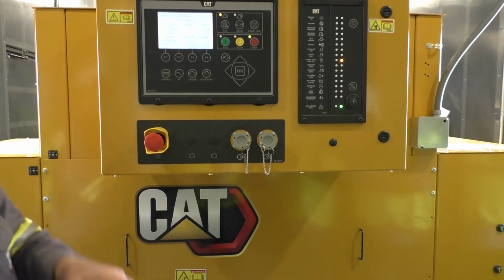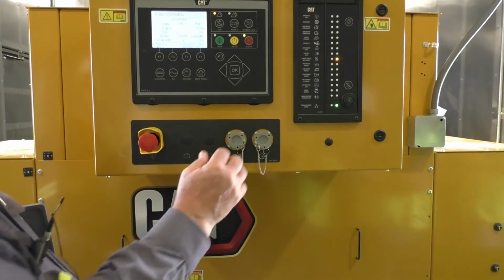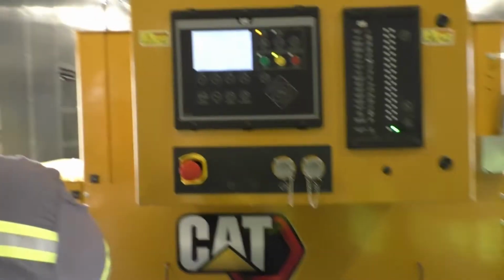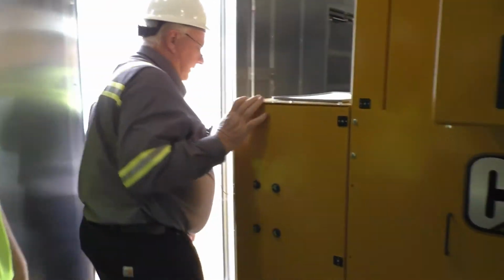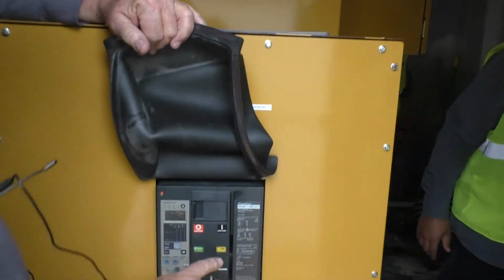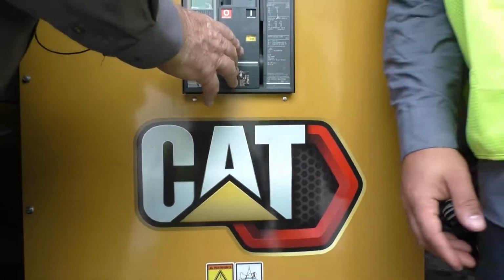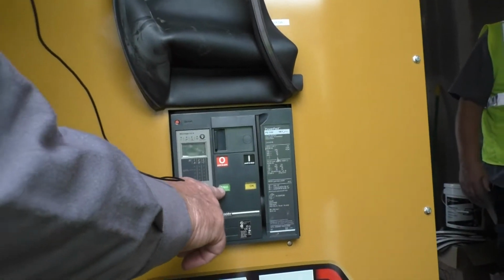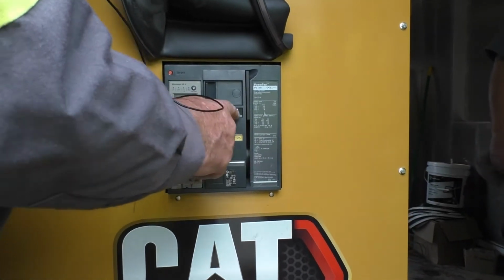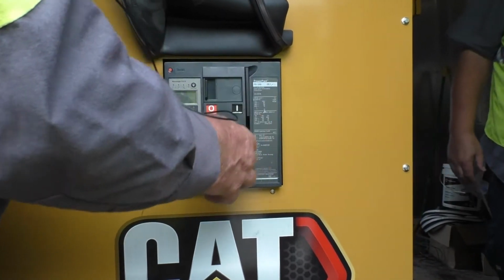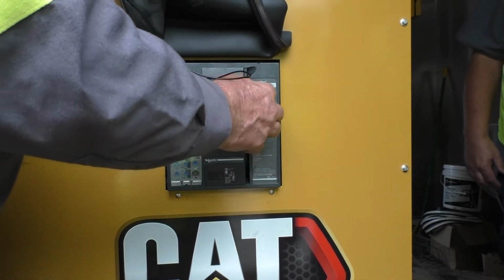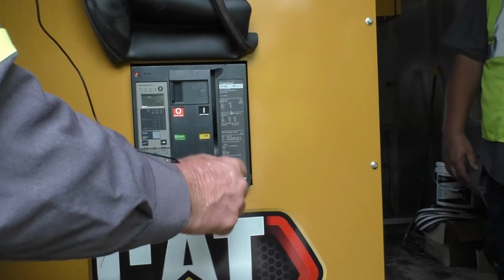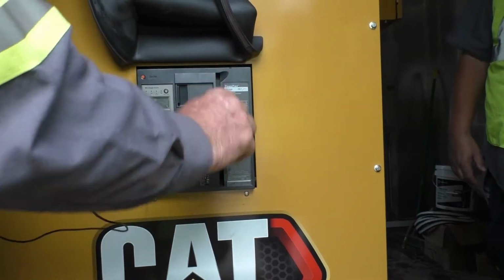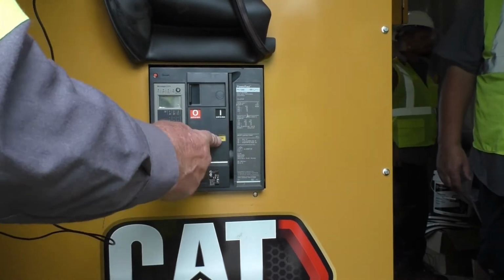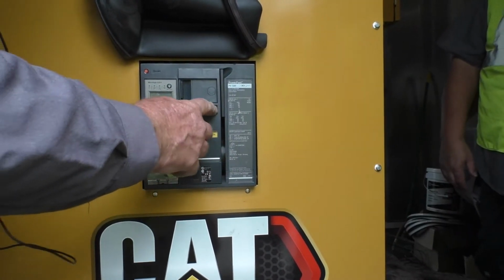the other thing we can do, and I'm sure you want to see it, is a transfer test. At that point, we just put this in auto. We're going to have to close this breaker. These are push buttons. On the breaker itself, it'll tell you the breaker's open, green, or if it's closed, it'll be red. You have two buttons, an open and a close button. If it doesn't charge by itself, say the charge motor goes bad, there is a charging handle. It's already charged, so you can't do it. But you'll just rack this until it gets free, and that'll change to an OK. And then you can go.